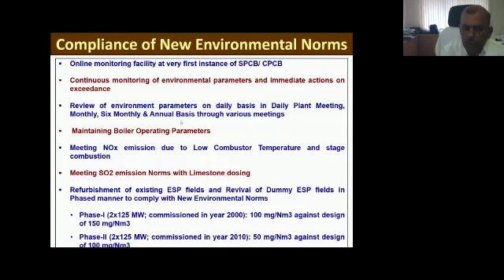Continuous monitoring of environmental parameters is done, and if there are some deviations or issues, like shutdown of units, ESP pass maintenance work, or in the monsoon feeding issues in lignite and lime, we immediately respond to the concerned pollution control boards with the reasons for deviations and actions taken. Then on a daily basis we are monitoring all these SOx, NOx, SPM parameters and taking corrective action. For achieving this, we have to maintain our boiler operating parameters so that they support the emissions. That is also being done on a regular and continuous basis.